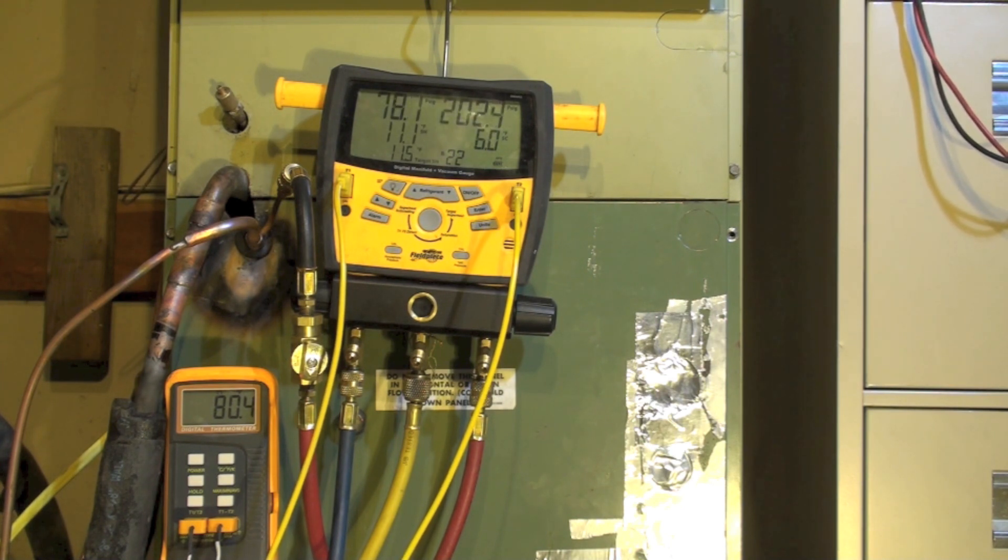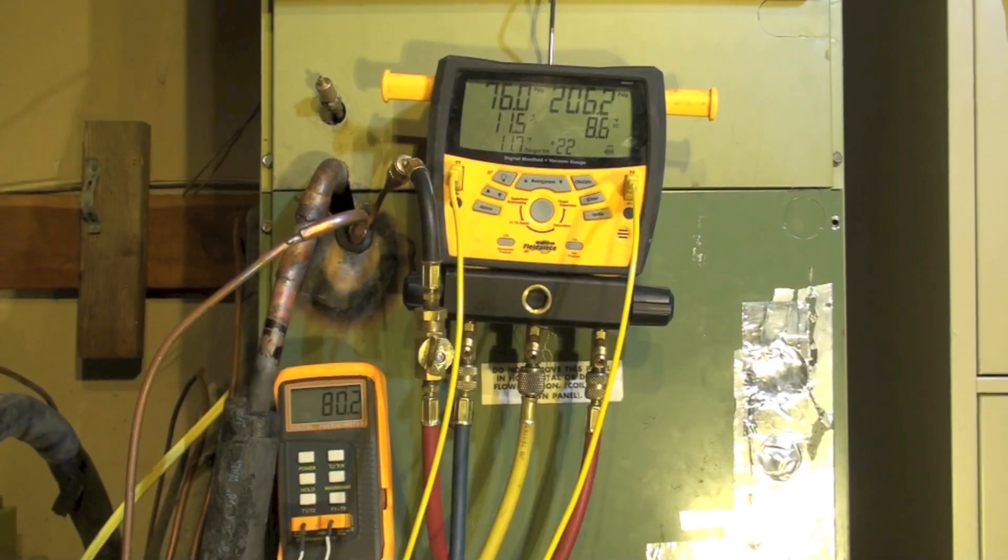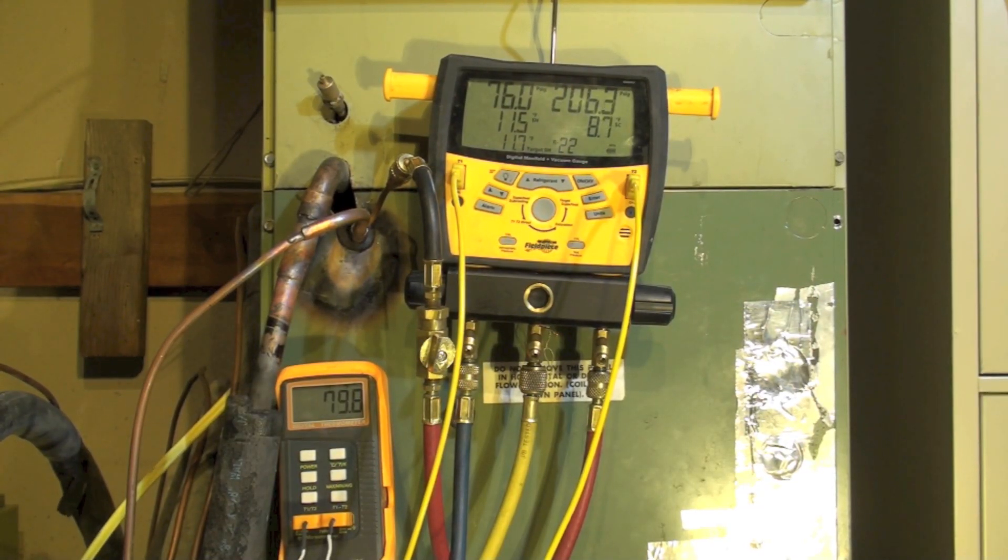Subcool 5.5, superheat 11.2. Target superheat is 11.5, so by weighing this in we actually got this thing pretty close. It looks like the temperature difference across the coil is about 21 degrees, so we're looking pretty good on this thing. That's a weigh-in charge.